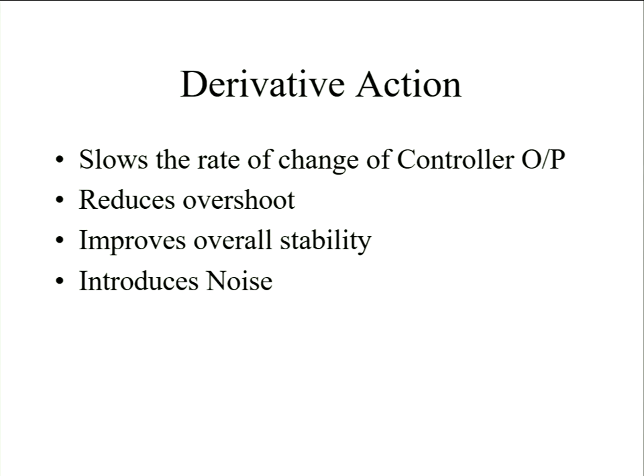and it comes off. So what I'm talking about with measurement, if I've got a flow signal, it might have noise like that. Now if I take the first derivative of that, say I'm doing it between there and there, I've got a change like that. Between there and there, I've got a change like that. Between there and there, I've got a change like that, and it tends to pick up that measurement noise.